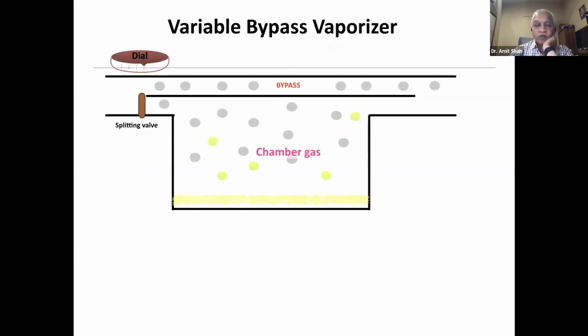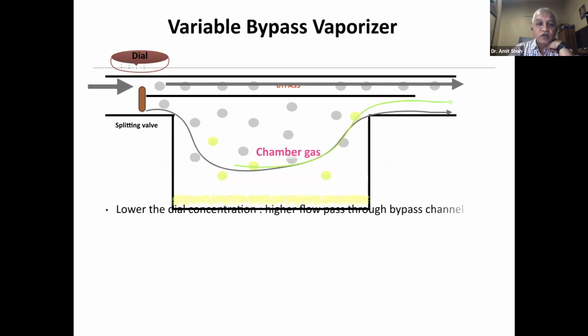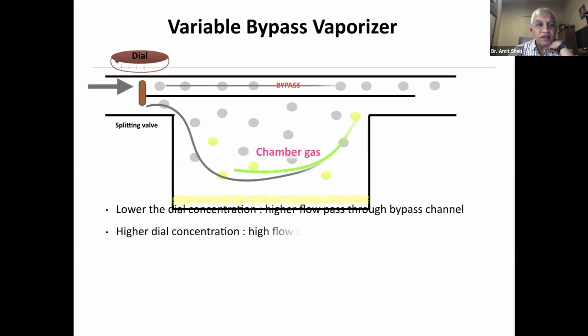Now let us go back to the variable bypass system. If it is switched on at 0, the entire gas will pass through the bypass. When you turn the dial, the splitting valve opens and allows some gas to pass through the vaporizing chamber, which takes away the agent there. If you lower the dial concentration, a small amount of gas passes through the chamber. If you increase the dial concentration, the splitting valve goes up, less gas passes through the bypass, and more gas passes through the chamber.